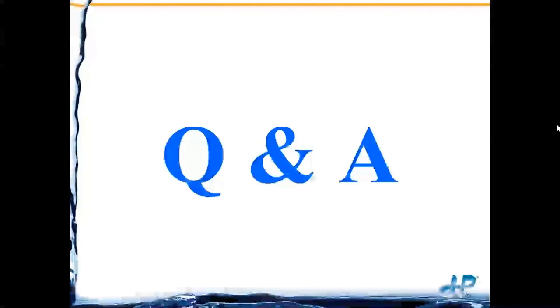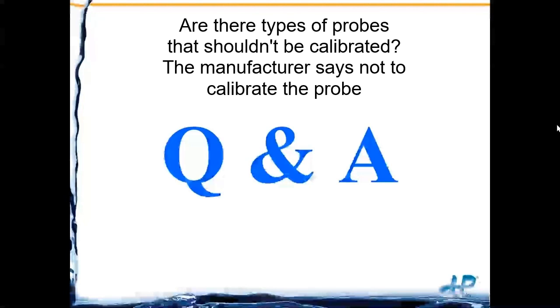Question: are there types of probes that shouldn't be calibrated — the manufacturer says not to calibrate? If a manufacturer is telling you not to calibrate your ORP probe, that's honestly a little questionable. An ORP probe is open to your process; if you don't correct for the coating and plugging occurring and don't calibrate, you will not get accurate readings. So yes, calibrate.